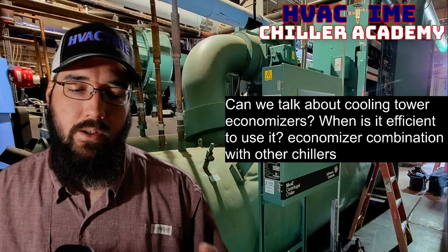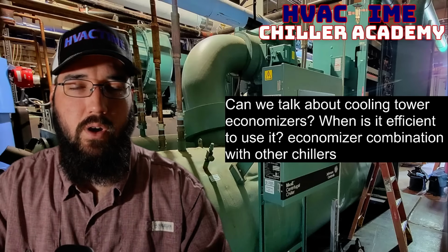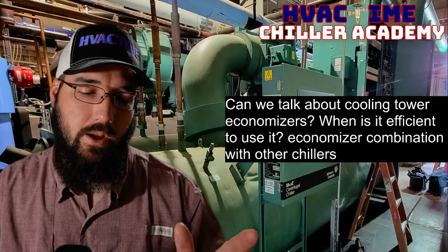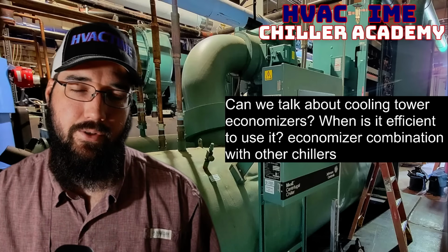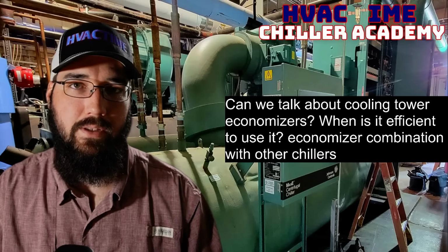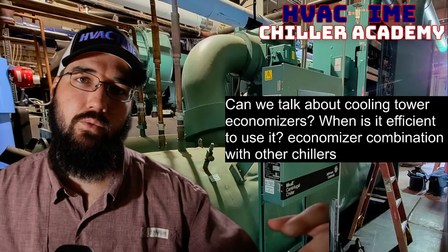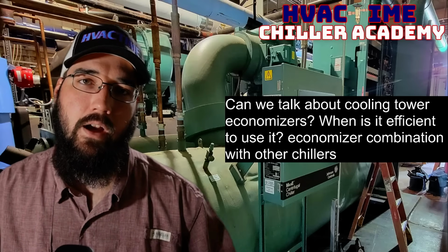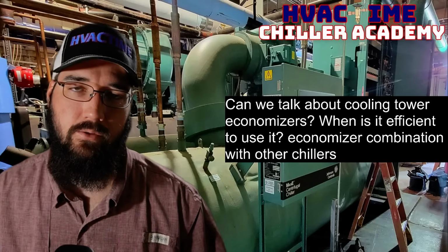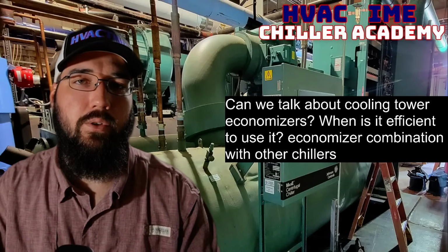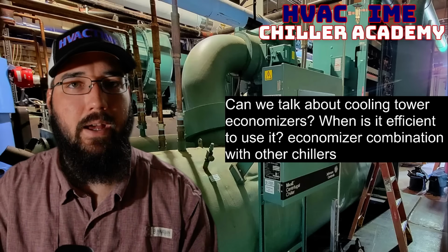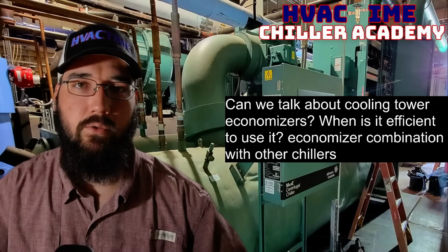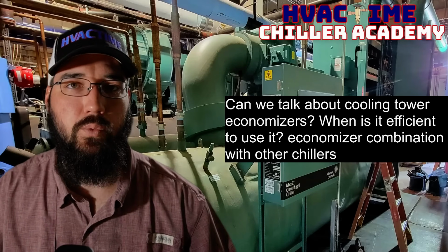Essentially, what we end up doing, we're going to process the condenser water through this heat exchanger. And what we'll have is a plated heat exchanger inside of the central plant. And that heat exchanger will process the chill water loop and the condenser water loop through it. Now, under normal mechanical cooling, so we're going through the chillers, we wouldn't utilize this heat exchanger. It would have bypasses installed usually that will completely divert around it and won't even process through it.